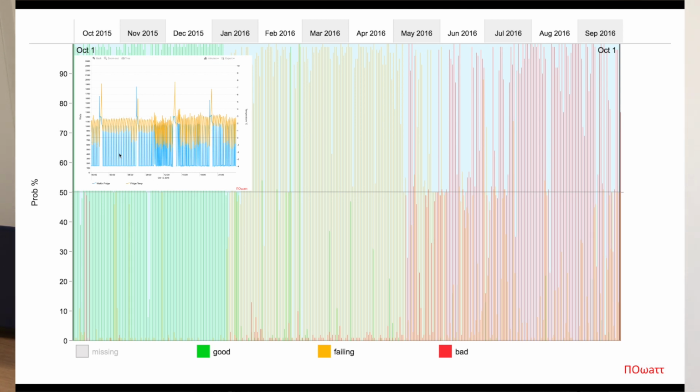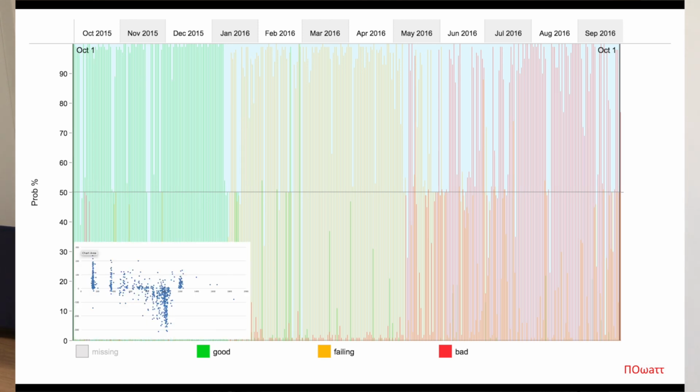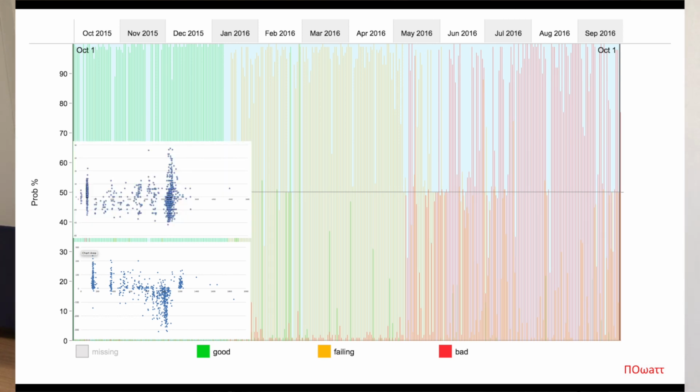So there was the good fridge. Looks a bit different to the one you saw, but again, it's quite normal. The compressor goes on and off and the temperature goes in correspondence. That's what it's seeing, and that was the pattern we saw before, yeah?